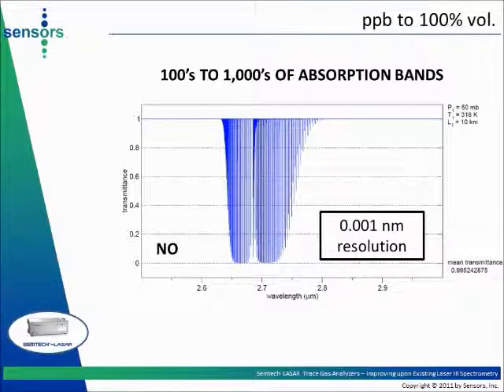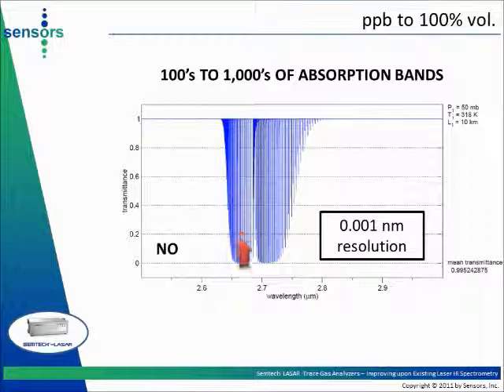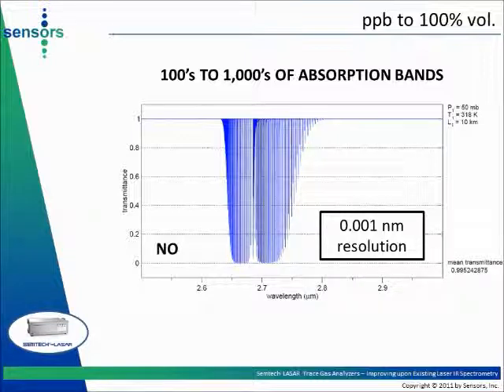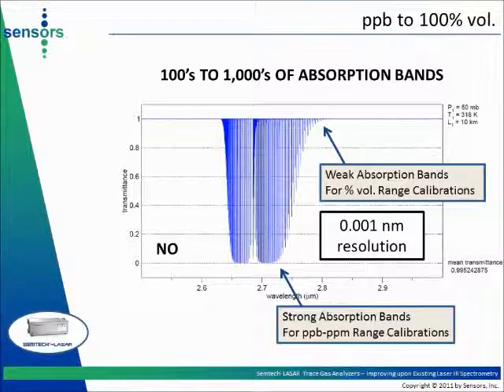The Semtech LASAR can be calibrated for trace concentration in high concentration ranges. The optical resolution of one picometer enables the observation of very narrow energy absorption bands. At that level of resolution, each gas features a large number of absorption bands in the infrared region, sometimes numbered in the thousands. Careful selection of the absorption bands measured allows calibration of the analyzer over wide ranges of concentrations. Weak absorption bands will be selected for high concentration calibration ranges; strong absorption bands will be selected for trace concentration calibration ranges.